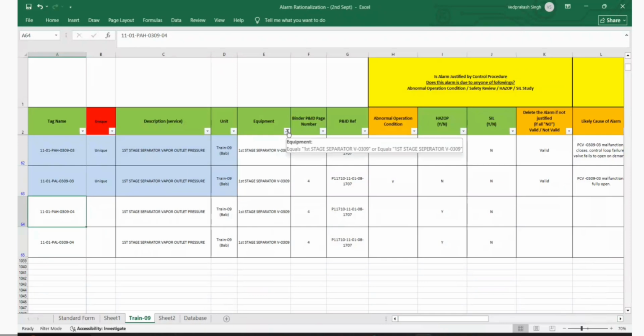Now my question, Mr. Chairman, I think like we discussed yesterday, if the alarm is linked to the control loop, while the control loop is the root cause of the high pressure or low pressure, shall I take credit for this alarm? Like we discussed yesterday? No, we concluded yesterday that when there is an alarm on high pressure, low pressure, we will not say control loop failure.